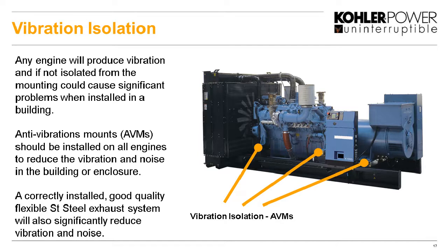One of the things also to note is the generator has its exhaust pipe bolted on, and if that wasn't isolated as well from the vibration, again, we'd have significant noise coming through from vibration through to the actual exhaust silencer as well. So we have to make sure the exhaust system has a good quality flexible steel joint between the exhaust and the actual engine itself.